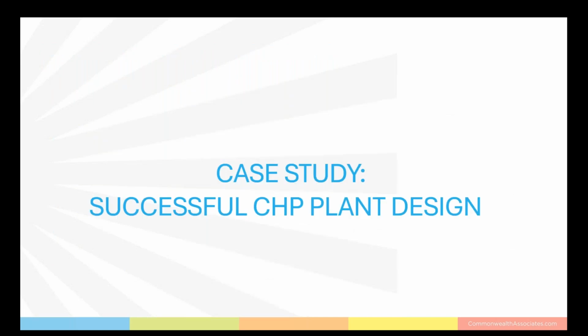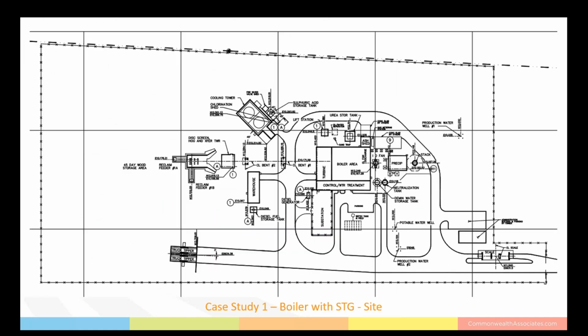So let's look at some case studies of successful plant design. This site is in the part of the country where there's a thriving forestry industry. So with regards to proximity to fuel sources, it's literally within a 1.5 mile drive for the trucks to move wood pulp from any of the 3 nearby sawmills to the truck tippers on site. Proximity to water, they have 3 wells on site, 2 for production and 1 for potable water. Proximity to energy demand, their power goes directly to a local grid through a switch yard within a mile of the site. And accessibility, the site is within 2 miles of a major highway, and as mentioned, close to the fuel source for the wood pulp.